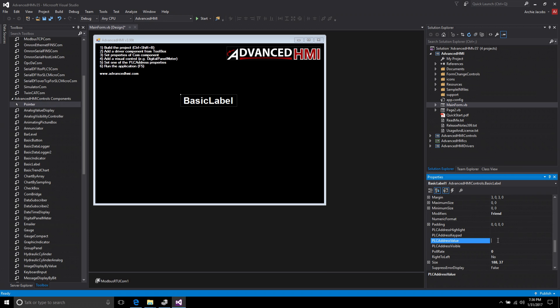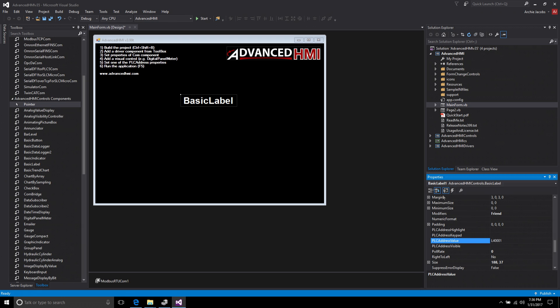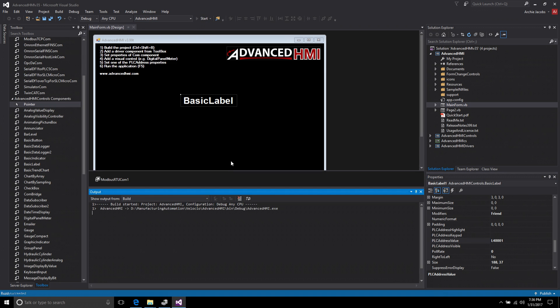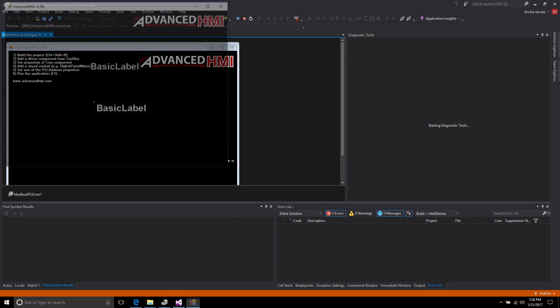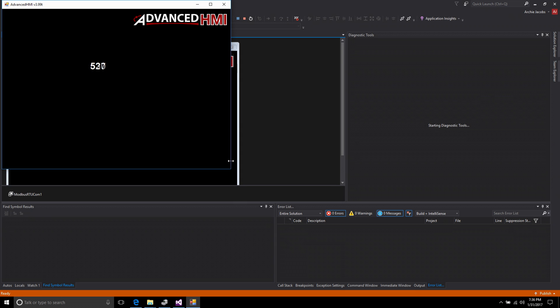So now what I want to do is use this basic label to show my timer. Remember I put in a timer and I mapped it to Modbus address one. In the Modicon world that address is going to be a 4000 series because it's an integer. Now if we remember it's a double integer, it's a 32-bit. Your basic addresses in Modbus are 16-bit. So in order to tell Advanced HMI we want to read a 32-bit, we're going to prefix this with an L. We're going to say this is a long integer, 32-bit. So we're going to do L4001. The 4 means it's the integer space and the 1 is the first register.